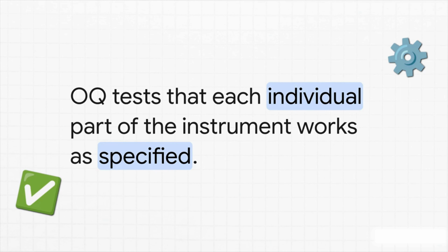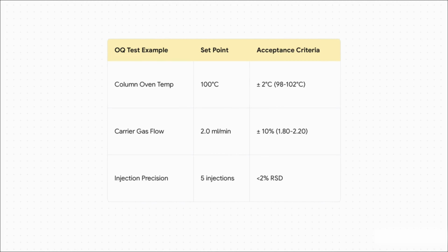So once it's set up correctly, we move on to operational qualification, or OQ. Now we finally get to power it on and test every single function, module by module. Can the oven heat up to the right temperature? Is the gas flow controller accurate? We test each component all by itself to prove it meets its own specifications. And look, these aren't just vague checks. OQ tests are super rigorous with predefined, non-negotiable limits. For example, if we set that column oven to 100 degrees Celsius, we need documented proof that it stays within, say, plus or minus 2 degrees. If it hits 102.1, it fails, period. The entire process stops right there until it's fixed.